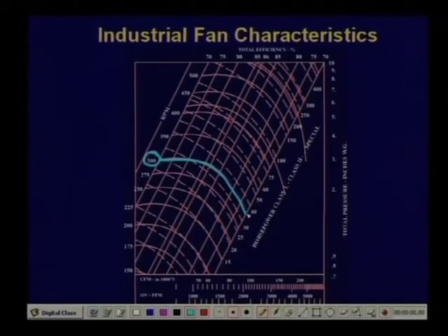So you see that it is somewhere over here, can you see that? Now, what is the power requirement here? Look at these curves: this is the constant 30 curve, this is the constant 40 curve, 40 horsepower. So where are we? We are at 35.